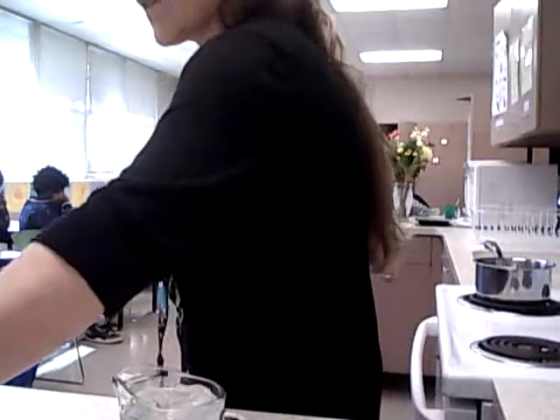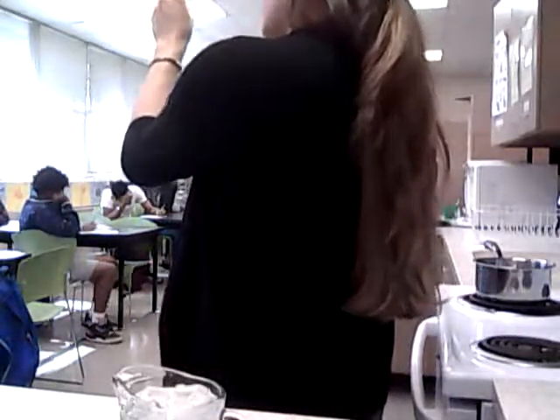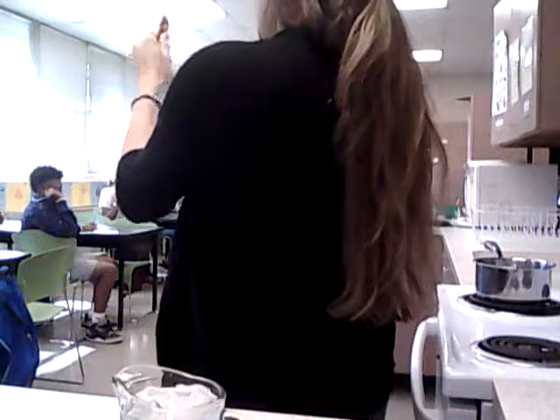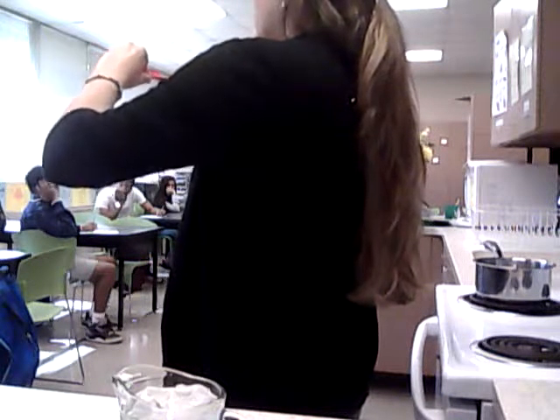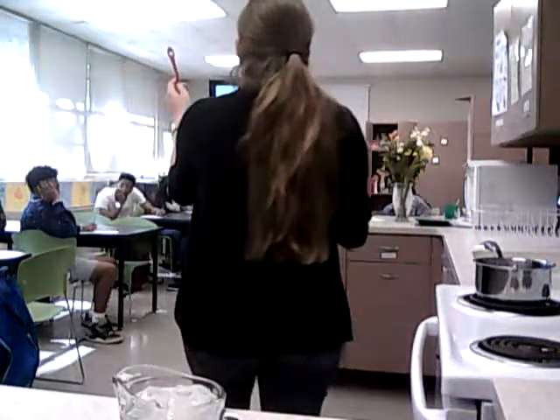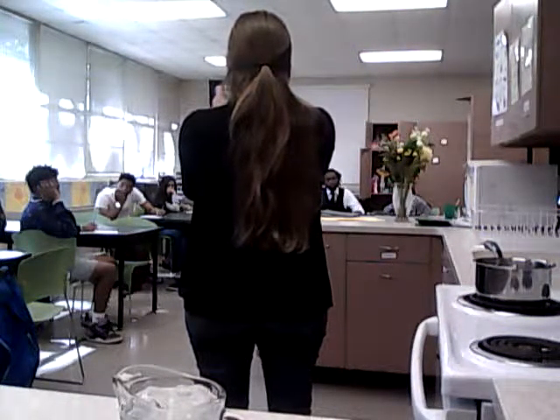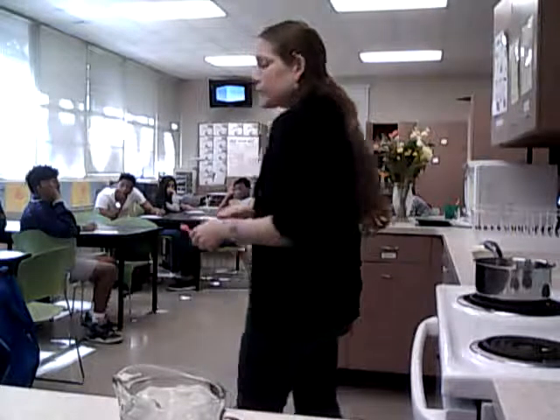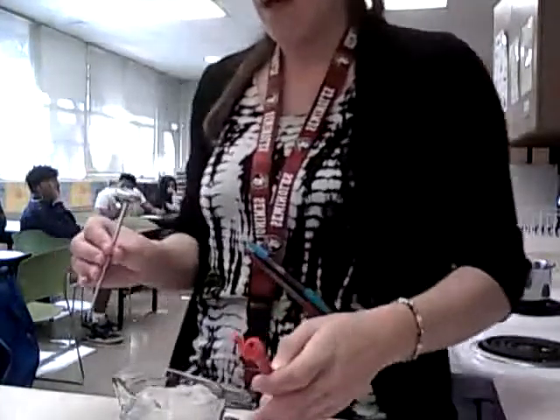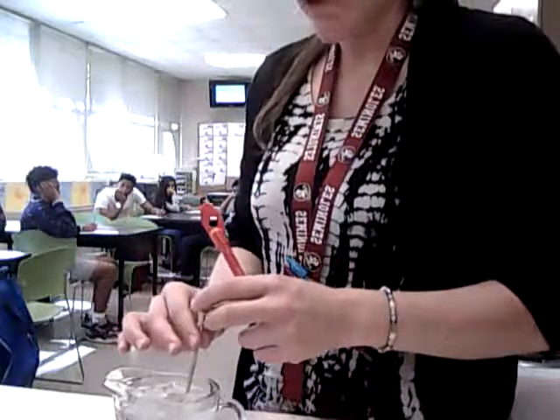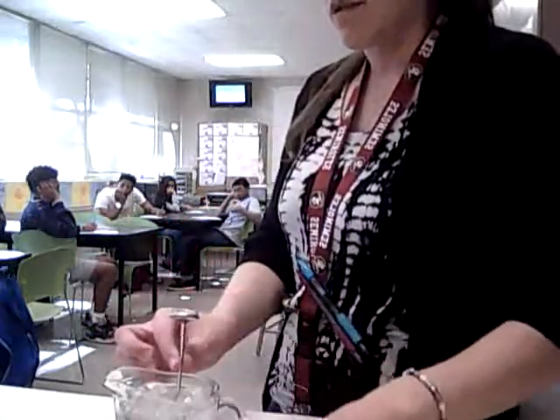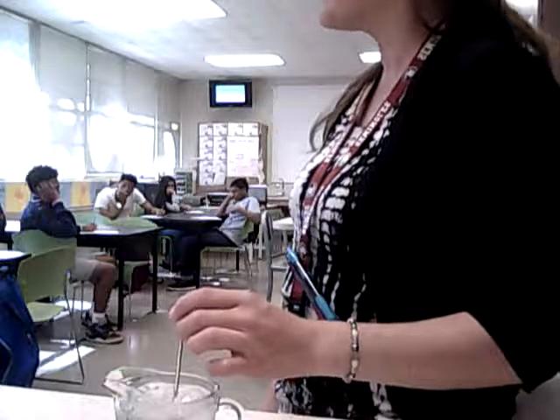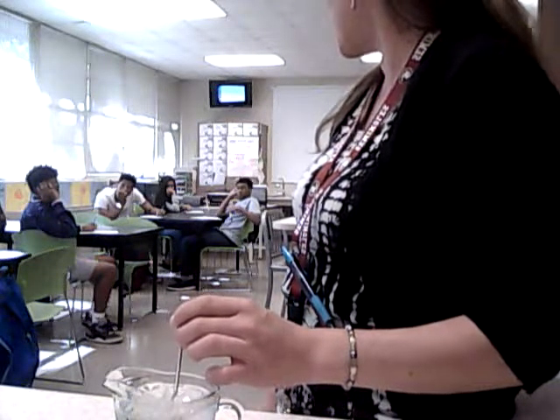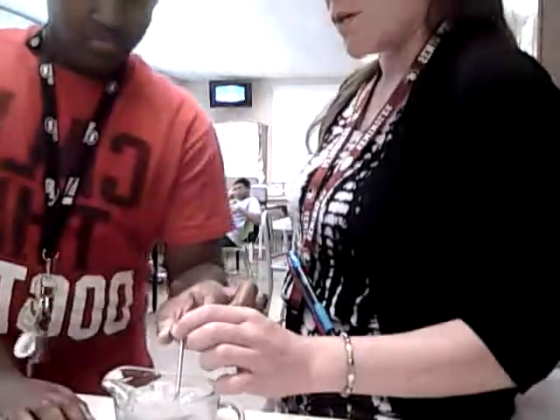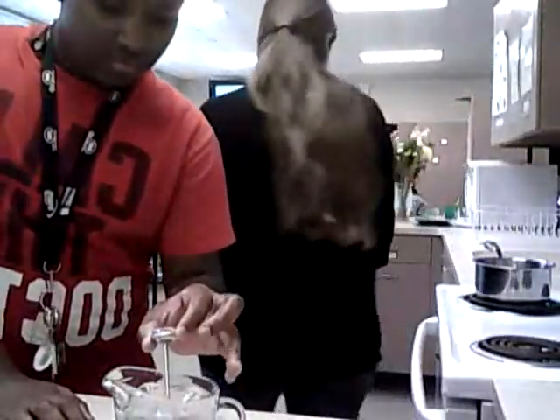All thermometers, if they're good ones, will come with a calibration unit on it, like this one does. You pull the thermometer out of its case. This calibration unit, you just move down to the end of it, and that shape is the exact shape of the calibration nut underneath the head of the thermometer. So we said freezing point is what? 32. Patrick, come on up here and tell me what this thermometer reads. You have to give it a minute. Wait till your needle stops moving, and then you know you've got an accurate measurement. So wait for that to stop moving and tell me what it reads.